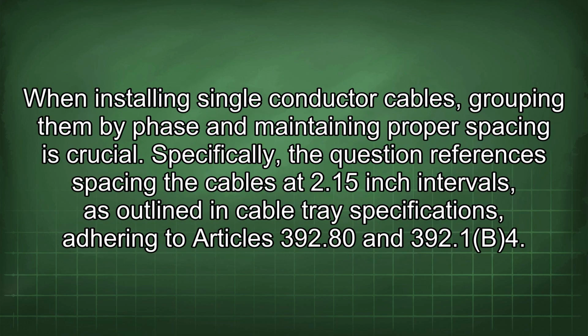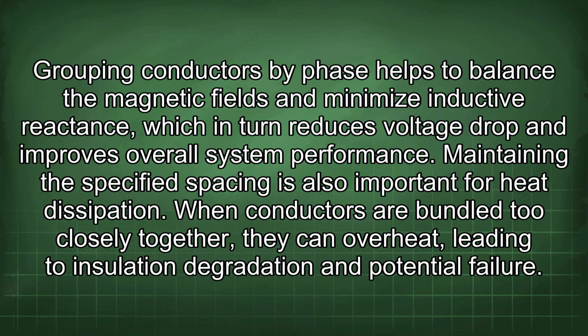When installing single conductor cables, grouping them by phase and maintaining proper spacing is crucial. Specifically, the question references spacing the cables at 2.15-inch intervals, as outlined in cable tray specifications, adhering to Articles 392.80 and 392.1b4. Grouping conductors by phase helps to balance the magnetic fields and minimize inductive reactance, which in turn reduces voltage drop and improves overall system performance. Maintaining the specified spacing is also important for heat dissipation. When conductors are bundled too closely together, they can overheat, leading to insulation degradation and potential failure.